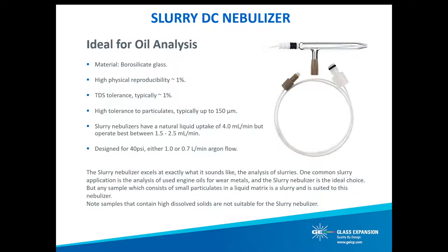Any sample which consists of small particulates in a liquid matrix is a slurry and would be well suited for this model. It's important to note, however, that samples containing both small particulates and high dissolved solids would not be a good choice for the Slurry nebulizer, due to its low tolerance to dissolved solids.